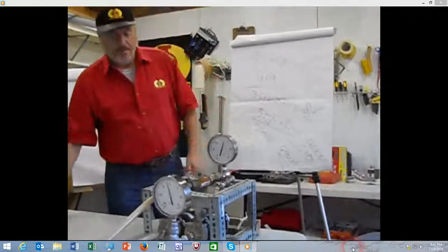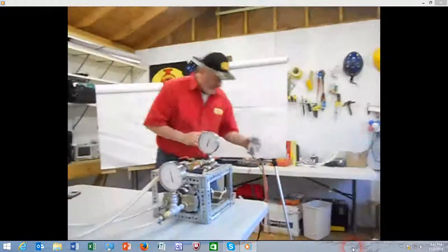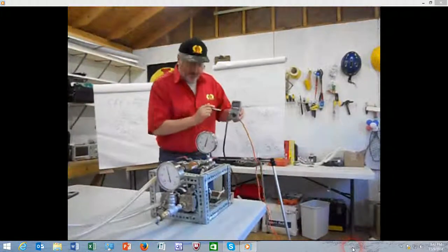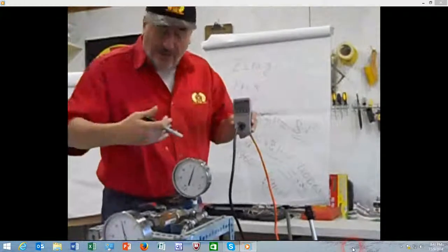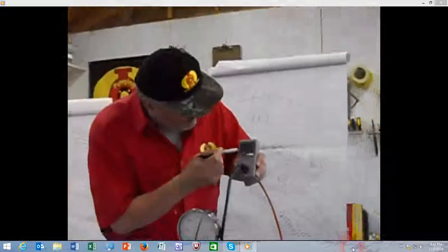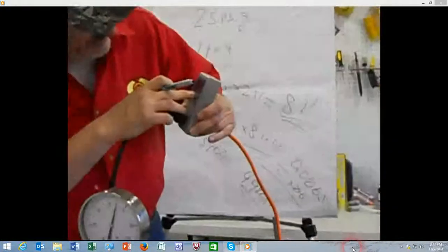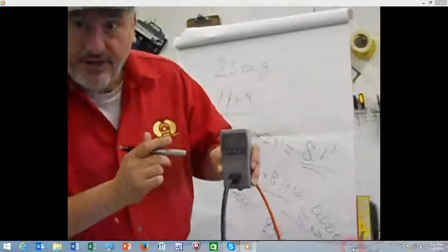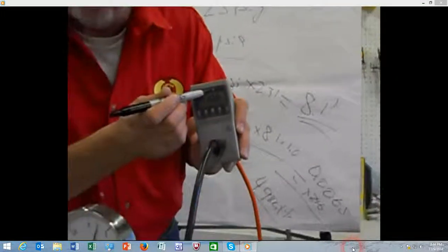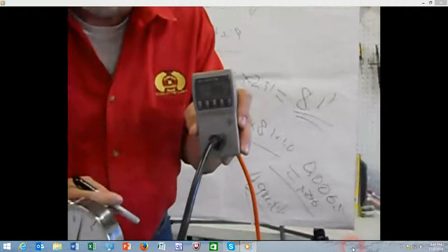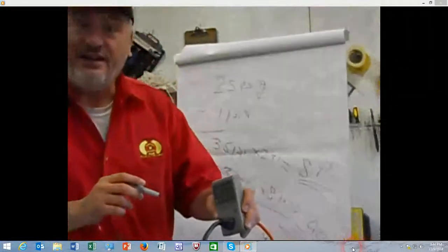4.9 watts. The total power is measured by the power meter that is connected between the power supply and the motor to the pump. It is registering 108 watts. 108 watts. So we're going to write it down.